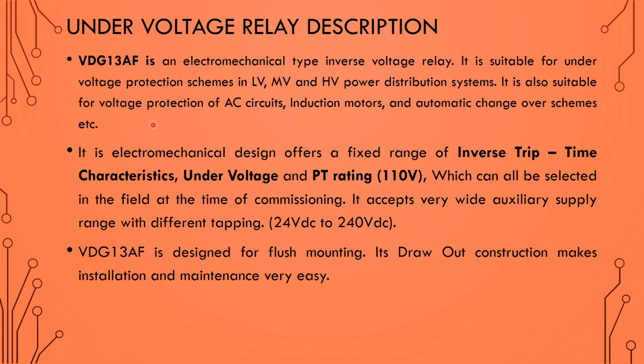The VDG13AF relay is an electromechanical type inverse voltage relay, that means an inverse characteristic relay, and it is suitable for under voltage protection schemes in low voltage, medium voltage as well as high voltage power distribution systems. In low voltage we will use it directly, in high voltage we will use it through the PT. It is suitable for voltage protection of AC circuits, induction motors, automatic changeover schemes, etc. Its electromechanical design offers a fixed range of inverse trip time characteristic. That means all electromechanical relays, which have clock setting, give you an inverse trip time characteristic.